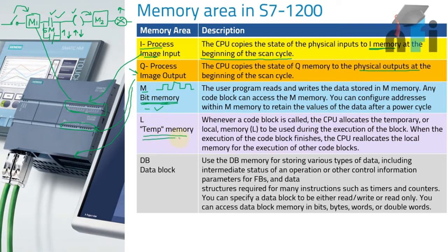Then you have temporary memory. When you have a lot of inputs and outputs, the PLC sometimes stores the result in a stack — a group of memory allocated for processing the information. We call it local memory or temporary memory. It is used during the execution of a block; when execution finishes, the CPU reallocates the local memory for other code blocks, so it gets cleared and can be used for another process.